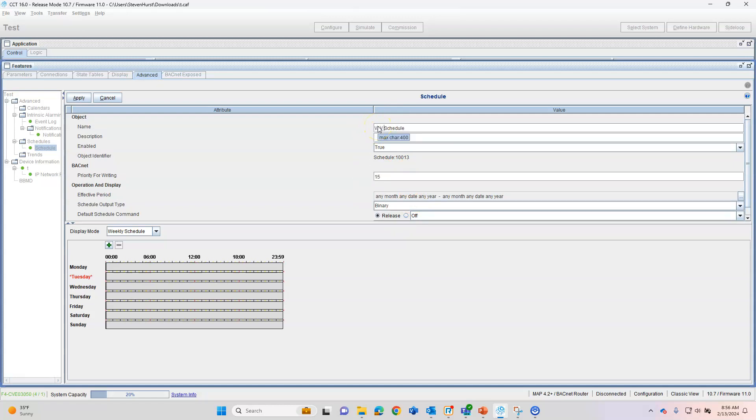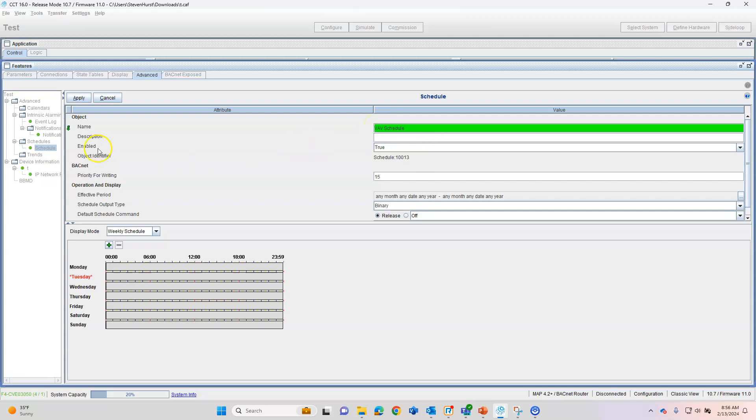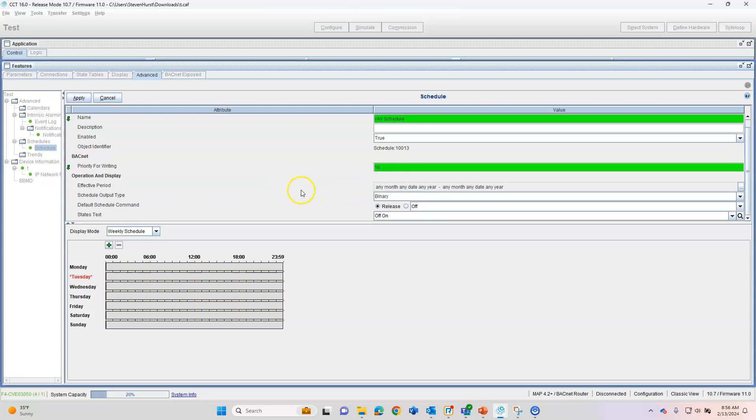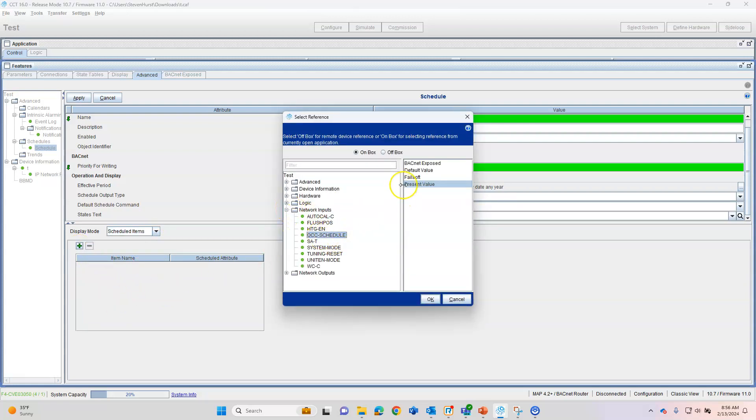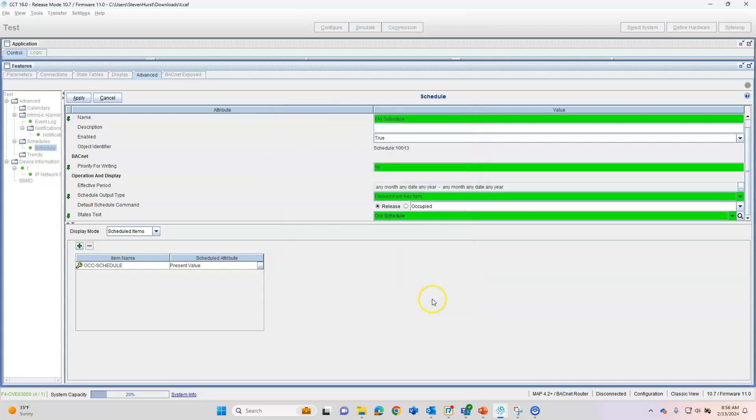I'll just put VAV in front of schedule there. Obviously, we want to enable BACnet priority. We can write it at whatever BACnet priority from 1 to 16. Scheduled object type, I'm not going to touch that yet. I'll show you why. If we start down here at display mode and go to Scheduled Items and click on the plus and go to the item that we want to schedule, which will be the occ schedule in this case.